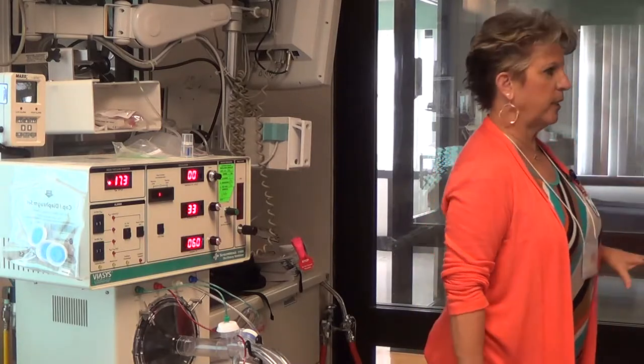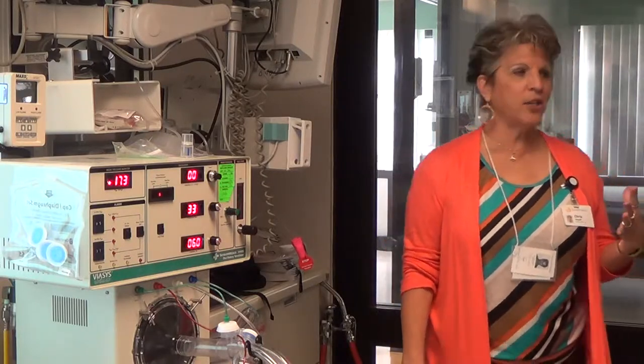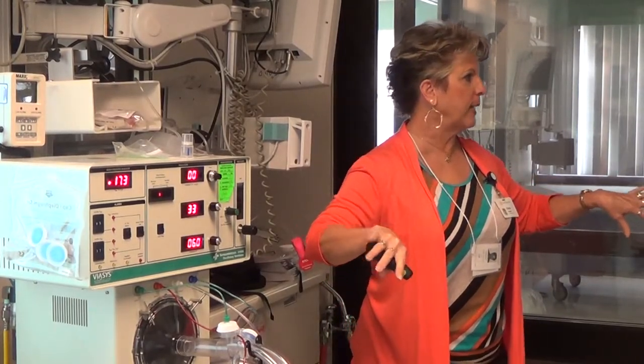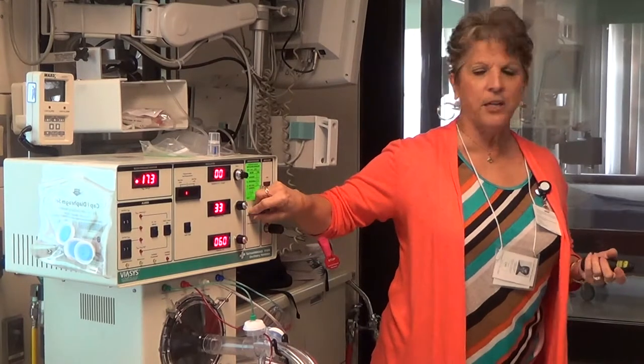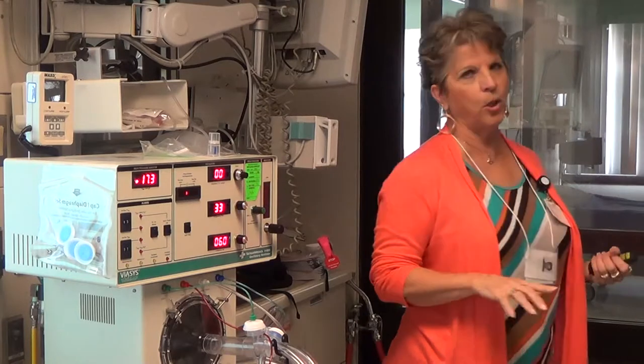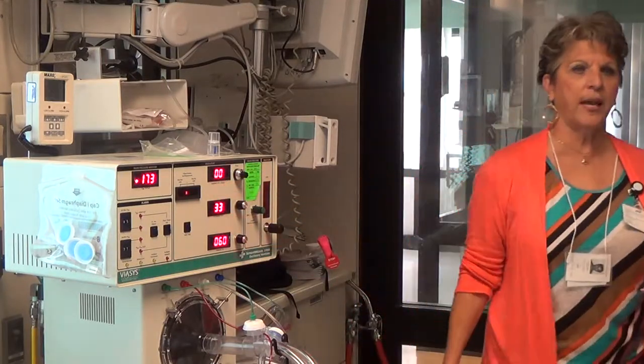Okay? You guys are all experienced users, right? I promise you, hopefully you learn one new thing today. We know oxygenation and ventilation, very unique to this ventilator, are totally decoupled from each other. Again, the only ventilator you'll work with that's true. Oxygenation is controlled by my mean airway pressure and my FiO2. Nothing else controls oxygenation. Well, almost nothing. We'll talk about that a little bit. Ventilation is controlled by my delta P, inspiratory time percent, and frequency. We'll talk about that a little bit more.